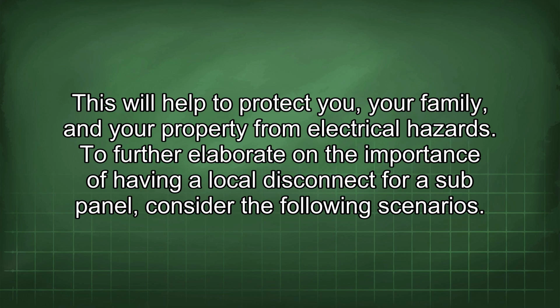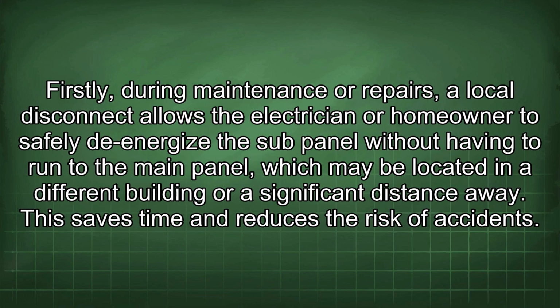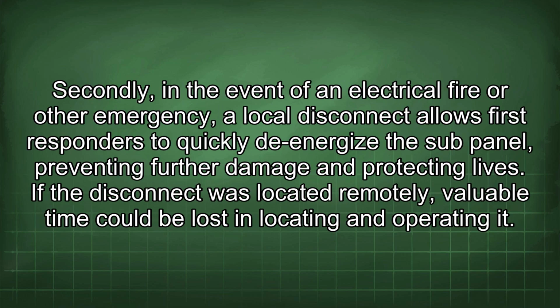To further elaborate on the importance of having a local disconnect for a sub-panel, consider the following scenarios. Firstly, during maintenance or repairs, a local disconnect allows the electrician or homeowner to safely de-energize the sub-panel without having to run to the main panel, which may be located in a different building or a significant distance away. This saves time and reduces the risk of accidents. Secondly, in the event of an electrical fire or other emergency, a local disconnect allows first responders to quickly de-energize the sub-panel, preventing further damage and protecting lives. If the disconnect was located remotely, valuable time could be lost in locating and operating it.